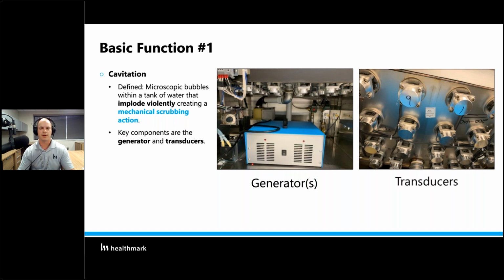All right. There's times now where I go around and into hospitals, and I still sometimes see an ultrasonic cleaner set to a cycle time of like 5 minutes. Well, a lot of times in today's sterile processing world, with how complex our surgical instruments are, 5 minutes just isn't long enough to really get that cleaning function adequate. All right. And in fact, a lot of IFUs that I've looked at, whether it's orthopedic instruments or robotic, a lot of times they even specify up to 15, 20 minutes for a standard ultrasonic cycle. So if you're still using 5-minute ultrasonic cycles, I just encourage you to go back, look at the IFUs of the instruments you're cleaning, and also to be running tests on them to make sure that they're actually performing this function adequately.